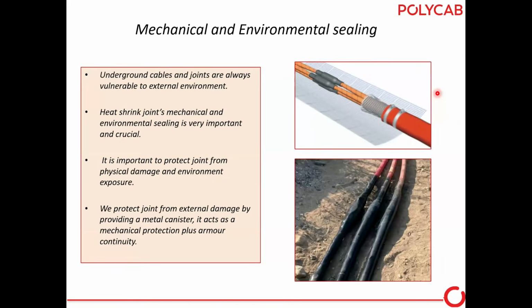Now, next the mechanical and environmental sealing. Like we have built the electrical insulation, over that the armoring comes. So what's the function of armoring? One function is that the short circuit current has to be passed or taken care of, and another is that mechanical strength has to be given to the cables. So we use the GI canisters, so that mechanical strength and short circuit current, or the continuity of armoring, is maintained.